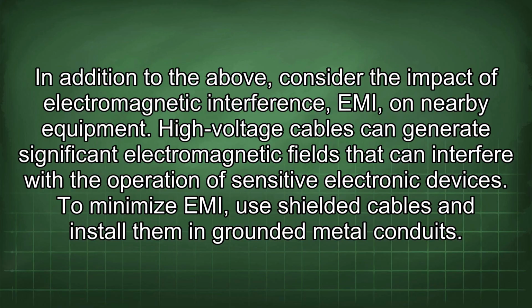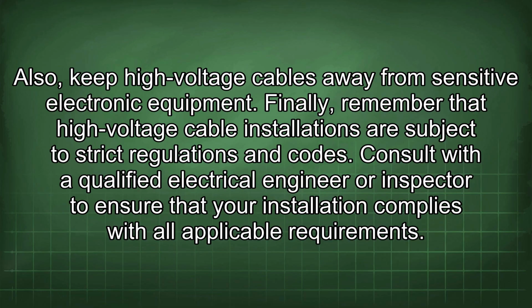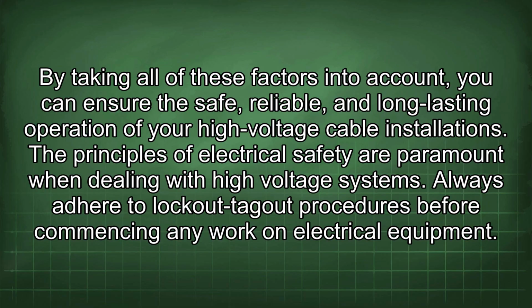In addition to the above, consider the impact of electromagnetic interference (EMI) on nearby equipment. High-voltage cables can generate significant electromagnetic fields that can interfere with the operation of sensitive electronic devices. To minimize EMI, use shielded cables and install them in grounded metal conduits. Also, keep high-voltage cables away from sensitive electronic equipment. Finally, remember that high-voltage cable installations are subject to strict regulations and codes. Consult with a qualified electrical engineer or inspector to ensure that your installation complies with all applicable requirements. By taking all of these factors into account, you can ensure the safe, reliable, and long-lasting operation of your high-voltage cable installations.